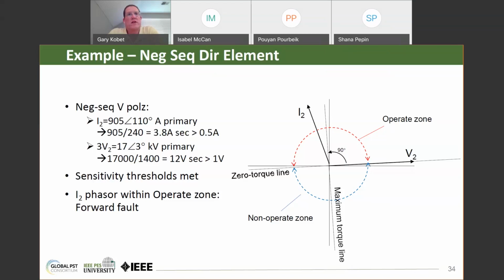But if you have, say, a 500 kV line in parallel with a 230 kV line, and there's a fault on the 500 kV line, there will be a ground fault, and there could be induced current in the parallel 230 kV line that could cause a misoperation for a zero sequence element. But with negative sequence directional elements, that's not an issue. So my experience at least is that the industry has been moving more toward negative sequence directional elements, but in cases where mutual coupling is not an issue, zero sequence could be used.